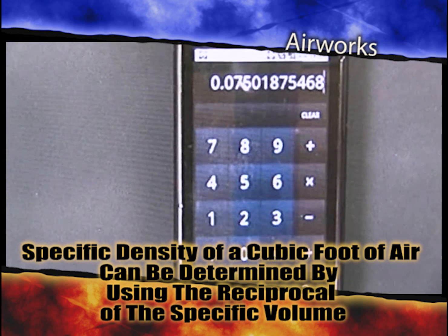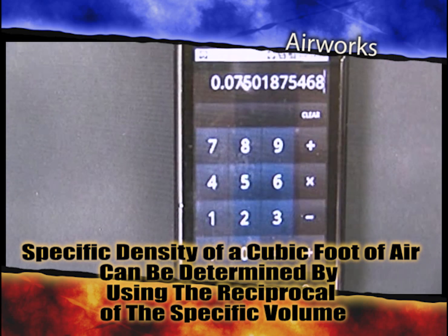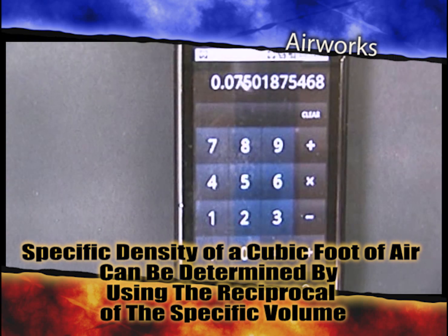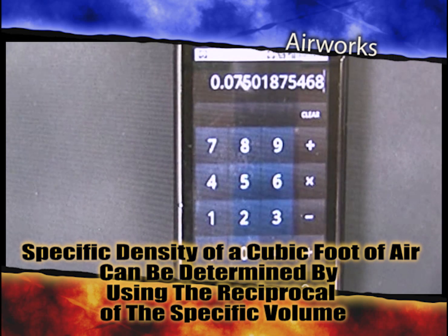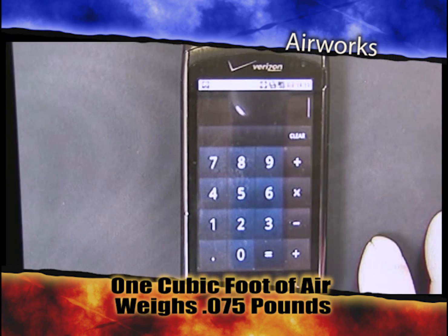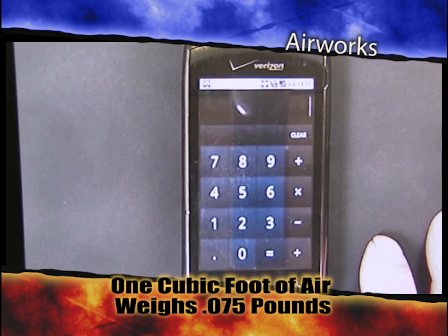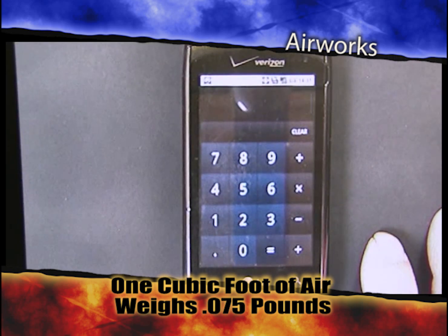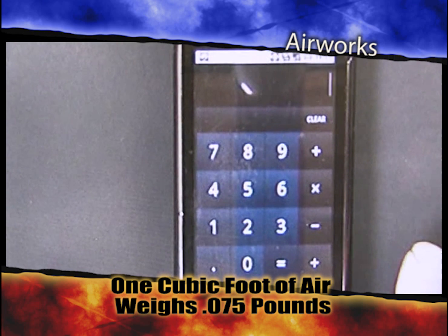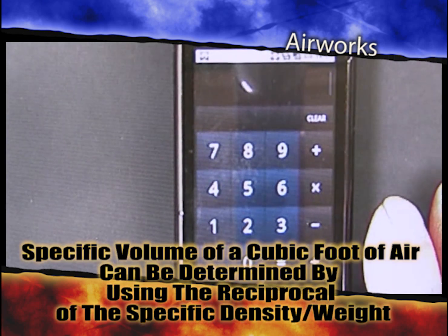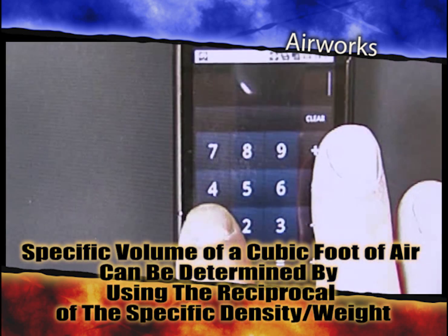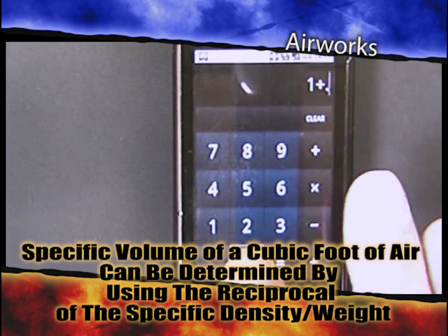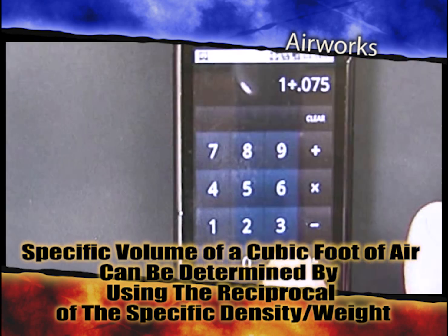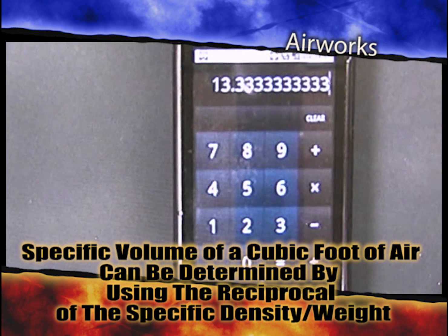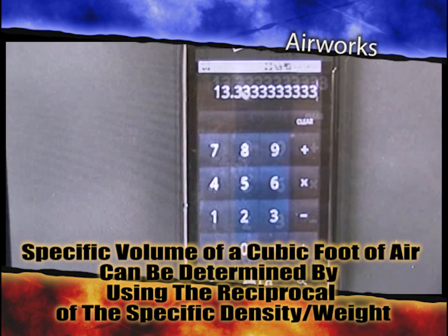Now if I wanted to reverse the process, by the way, 0.075 is the specific weight of 1 cubic foot, the specific density. Density, weight, same deal. So this is a specific density of a cubic foot of air. Now taking it from the specific density side, 1 cubic foot of air weighs 0.075 pounds. So if I want to know the reciprocal of that, which will give me the specific volume, I would calculate 1 divided by 0.075 equals, oh, it's magic, 13.33 forever cubic feet for 1 pound of air.